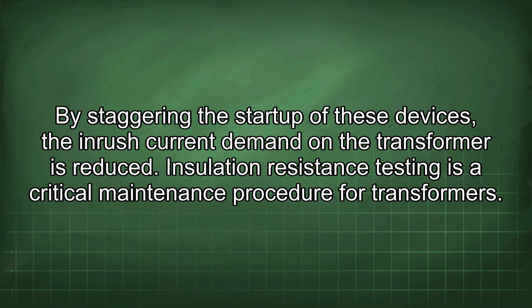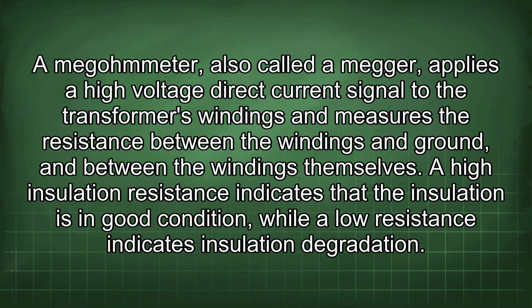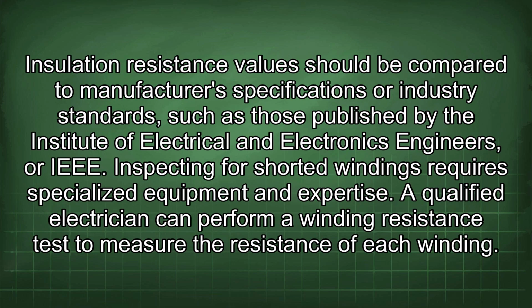Insulation resistance testing is a critical maintenance procedure for transformers. A megohmmeter, also called a megger, applies a high-voltage direct current signal to the transformer's windings and measures the resistance between the windings and ground, and between the windings themselves. A high insulation resistance indicates that the insulation is in good condition, while a lower resistance indicates insulation degradation. Insulation resistance values should be compared to manufacturer's specifications or industry standards, such as those published by the Institute of Electrical and Electronics Engineers, or IEEE.